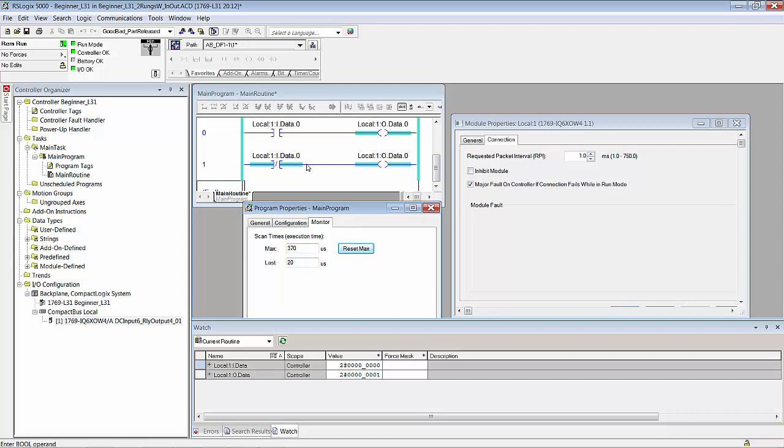At 5 milliseconds, the intermittent state was at a higher frequency and still discernible with the output LED device. But at 1 millisecond, I could hear the relay output chattering without any visible state change. Now, I don't have my relays chattering right now, but the output is on all the time. But remember, I also flipped my I/O. So now I'm going to put this back.